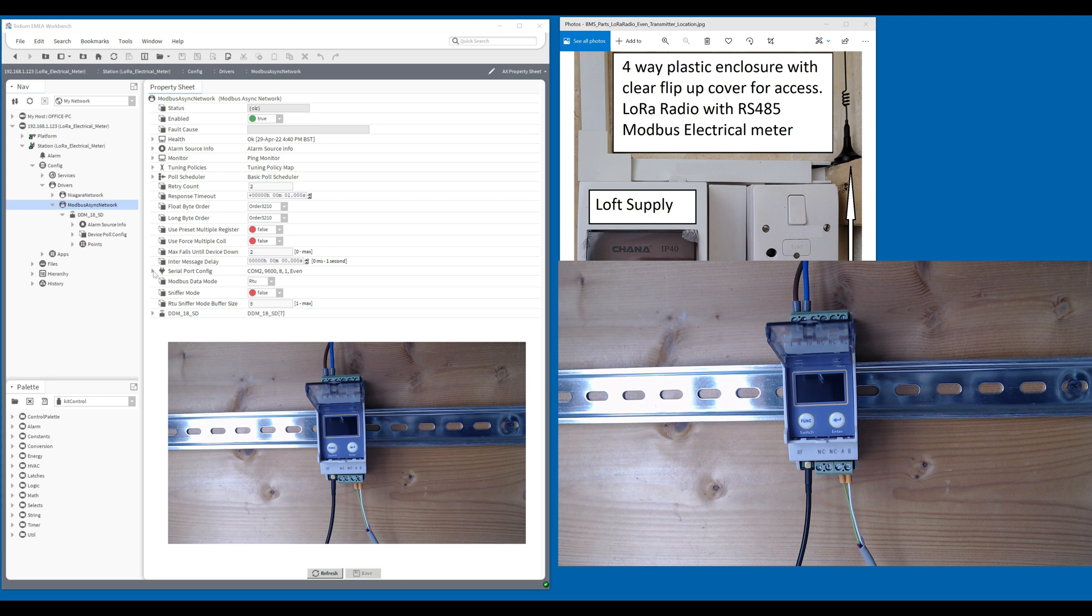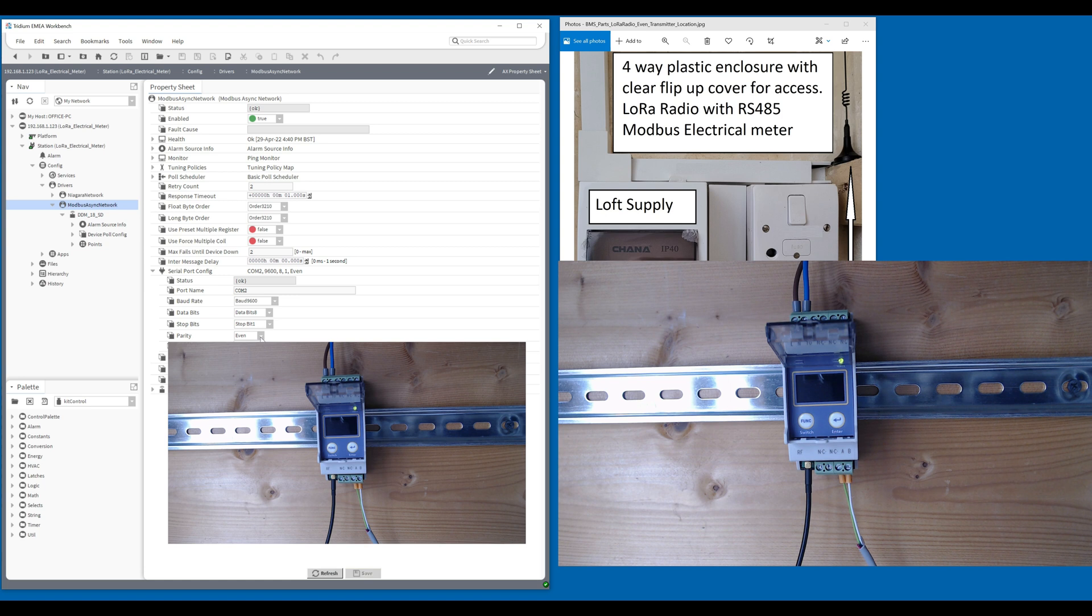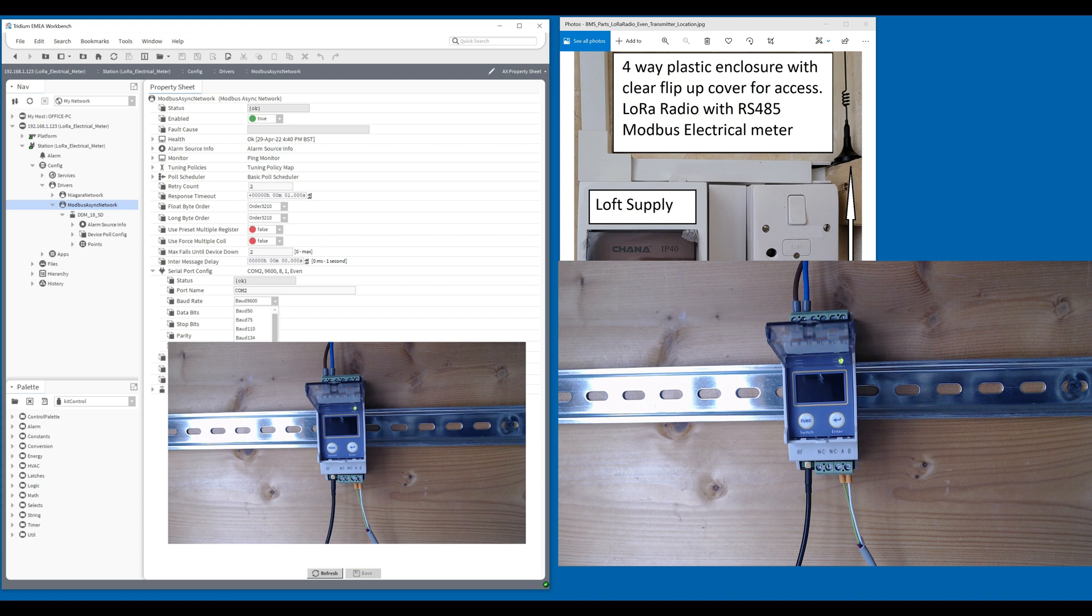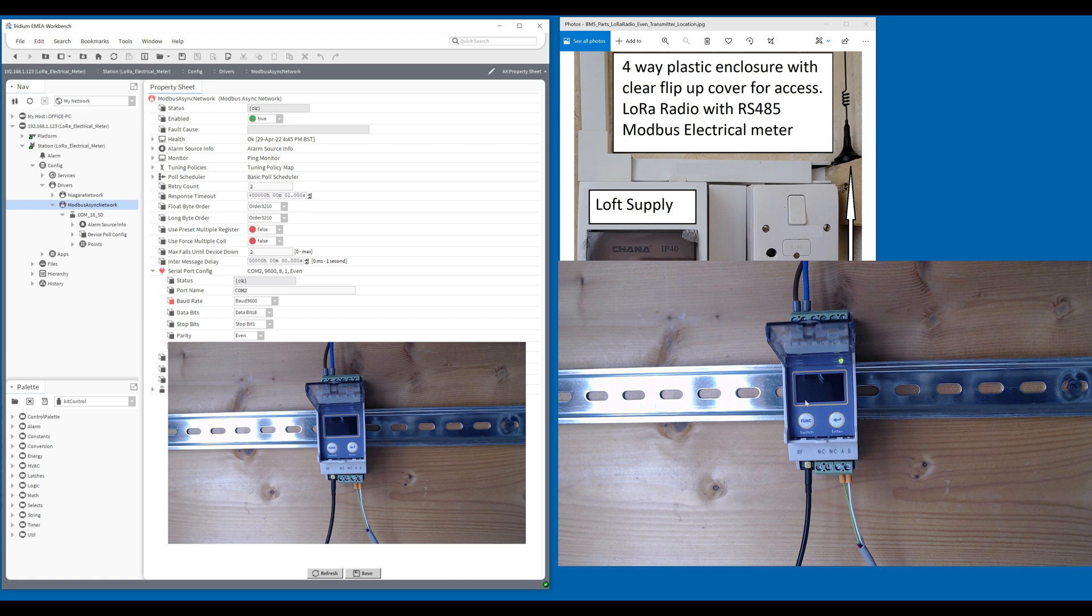You can see that COM2 is set up at 9,600 8-1 even. Some meters are also none, so that may need to be changed sometimes from even to none. But they're normally 9,600 factory. Very rare would you get 19.2 factory set. You would normally be 9,600 8-1. And this is your catch: sometimes it can be even, sometimes it can be none. You need to double check that. If your LoRa system doesn't work and bring the meter data in, then it may be worth changing the none to even or the even to none, depending on what your settings are.